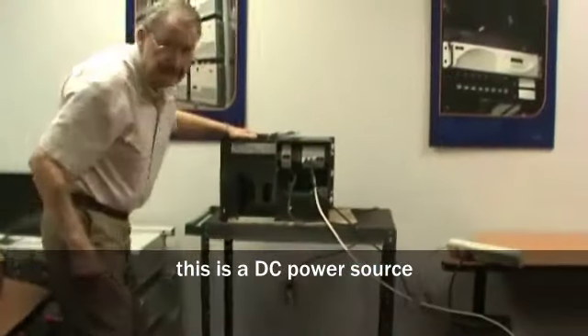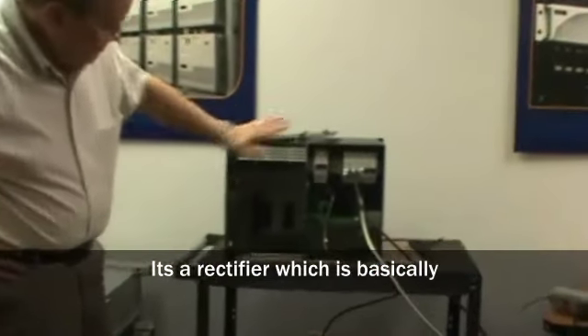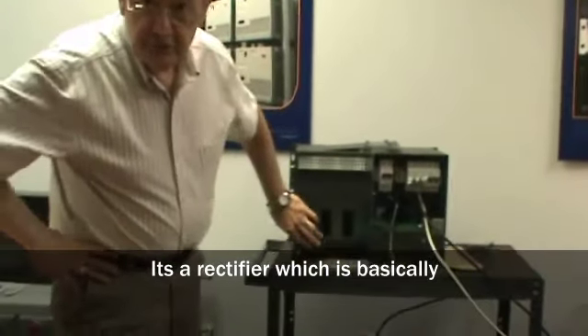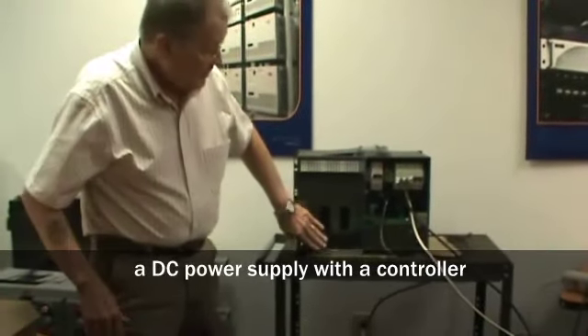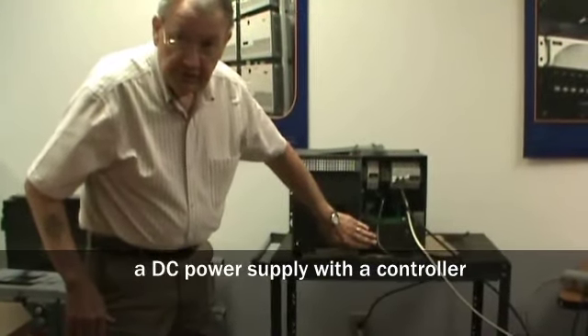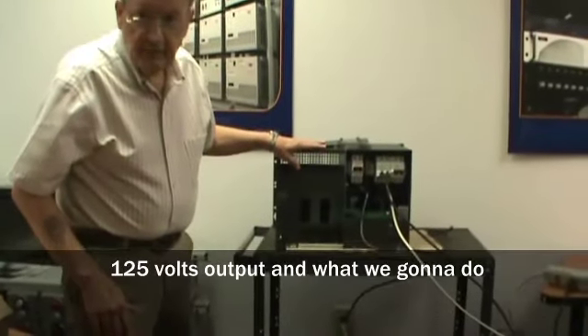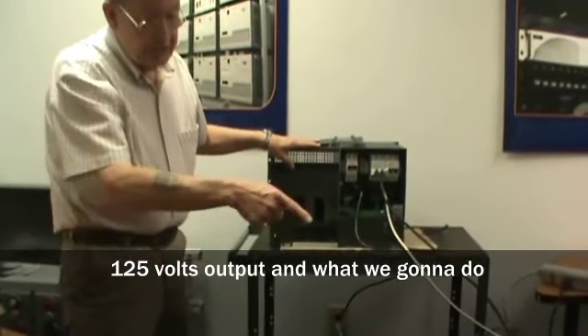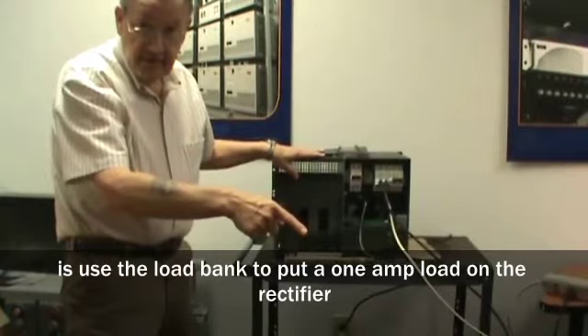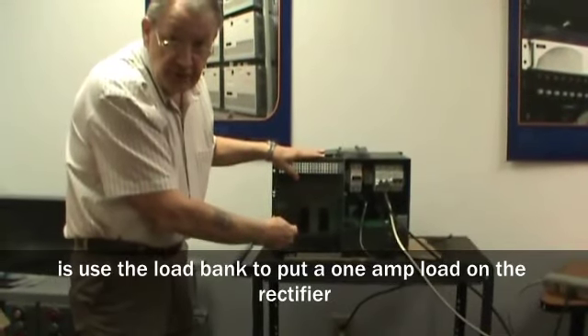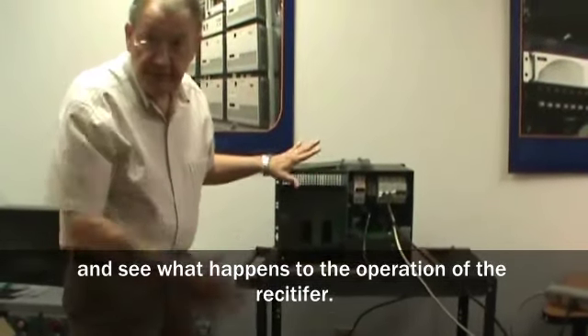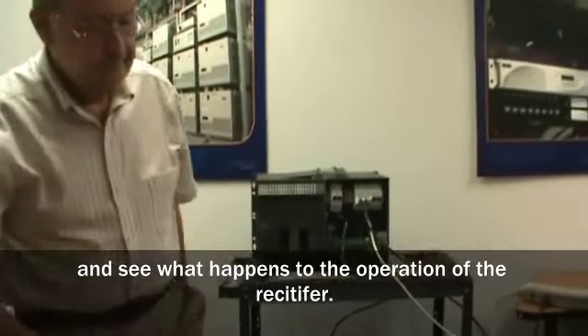This is a DC power source. It's a rectifier, which is basically a DC power supply with a controller. 125 volts output. So what we're going to do is use a load bank and put a 1 amp load on the rectifier and see what happens to the operation of the rectifier.